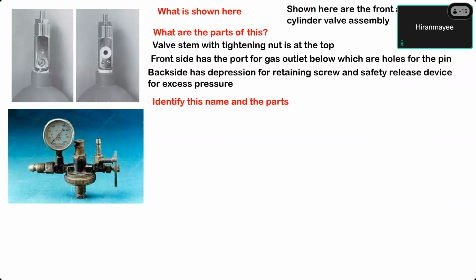45 to 55, sir. 45 to 55 is the wall outlet pressure, which comes to 400 kPa. This reduces to 14 to 15 psi. The pressure regulator reduces the pressure of 2000 produced by the cylinder to 14 or 15 psi.